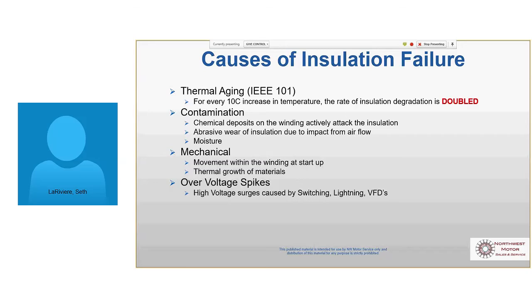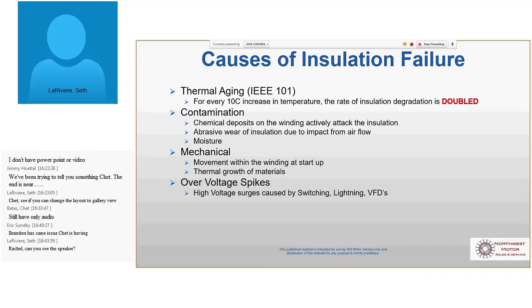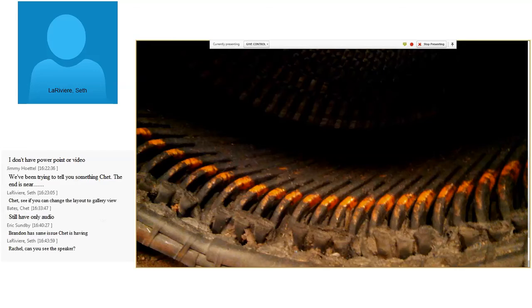Some contaminants are abrasive. We've got a customer that coats their product in cornstarch, and they're also pumping sugar, and sugar is really abrasive. You'd be surprised how abrasive sugar is, and if it gets inside the motor, man, it just creates havoc. And then the mechanical movement at startup that we talked about, all these things that introduce heat into the motor, they all happen. So that's why it's good to have a motor that's designed to take that.